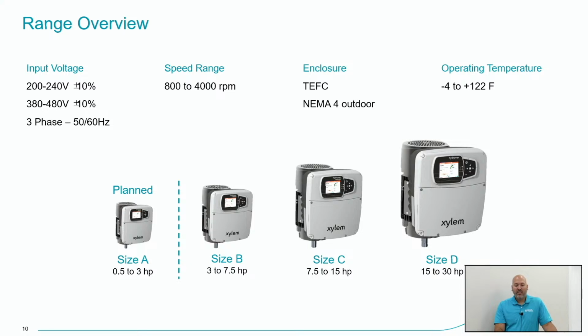Next, the motor itself has a speed range of 800 RPM to 4,000 RPM, so these are 4,000 RPM rated motors. It's a TEFC motor. The VFD has a NEMA 4 enclosure rating, so it can be used outdoors. The temperature there is the ambient temperature rating, so it can be in an environment from -4 to 122 degrees Fahrenheit and operate perfectly fine. There are 3 different frame sizes, as you can see along the bottom: size B, C, and D, with a few horsepower ranges, but as I mentioned, this can go from 4 horsepower to 30 horsepower.